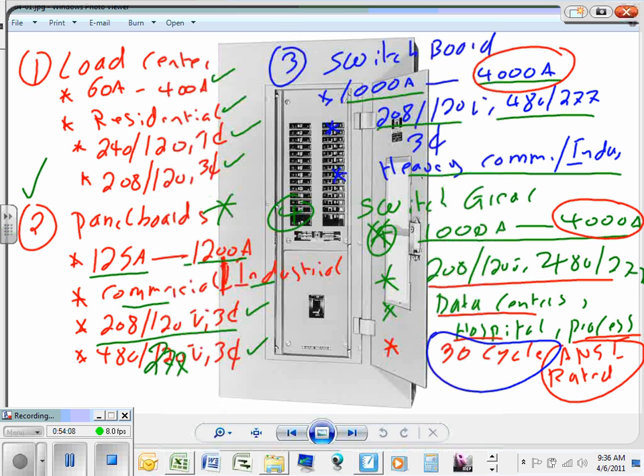Number one. Number two, they're rated for 30 cycles. So if you allow a half second short circuit, a 65,000 amp short circuit sitting in a panel, shaking that panel inside out and burning it, the panel is still sitting there. That's where the ANSI rated panel comes in. They're rated, they're insulated, they're robust, they're big, and some of them can go up to 100,000 amp rating. 100,000 amp at 480, short circuit for half a second, cooking this equipment, and when it trips, you go there and nothing has happened to any of these buses. The circuit breakers are robust enough to handle it. So that's the single most important thing about switchgear: the ability to handle a huge amount of short circuit without burning itself.